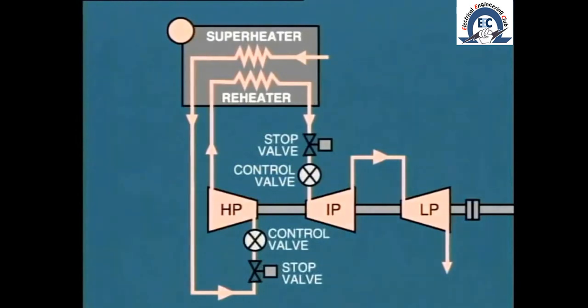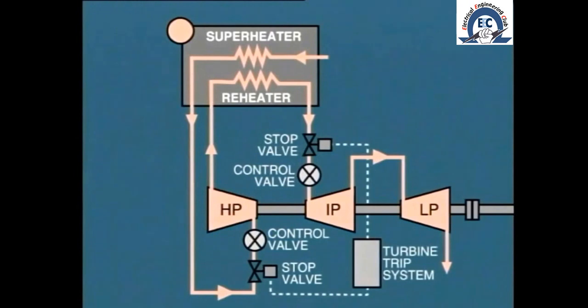On reheat turbines, an additional stop valve and control valve are located at the reheat steam entrance to the intermediate cylinder. We can see the arrangement here. The reheat stop valve functions in the same manner as the turbine main stop valve, and in fact, its operation is triggered by the same trip mechanism.